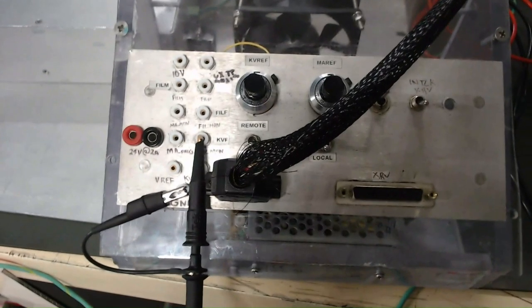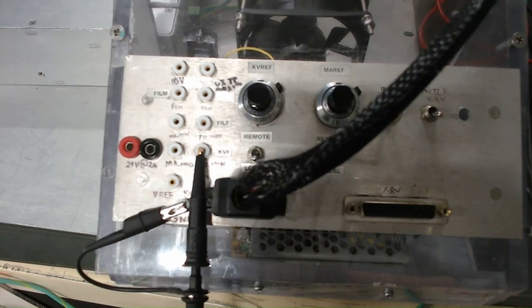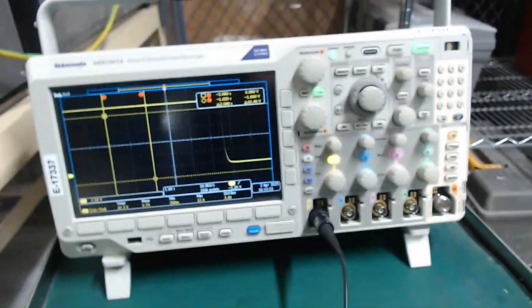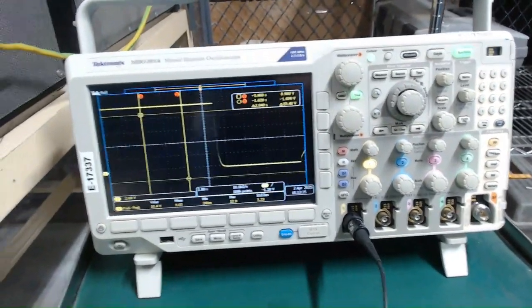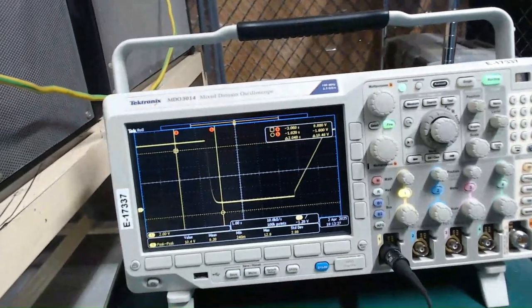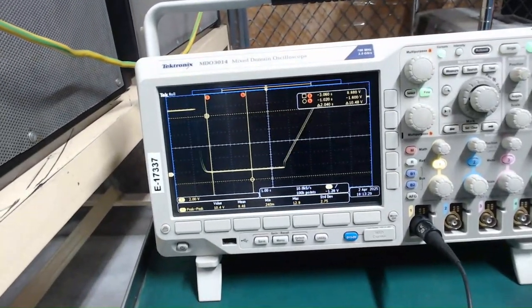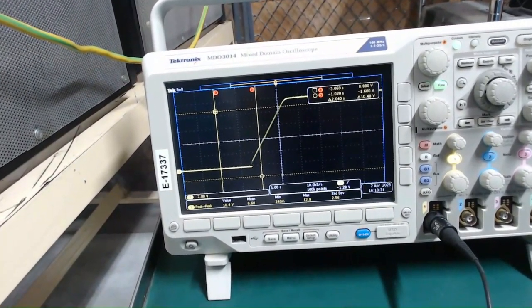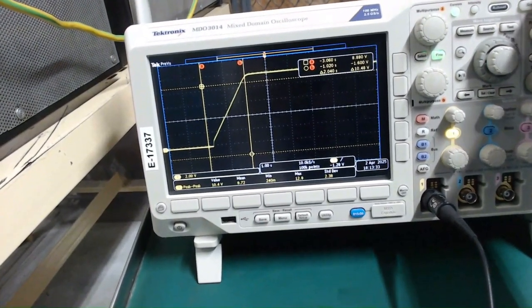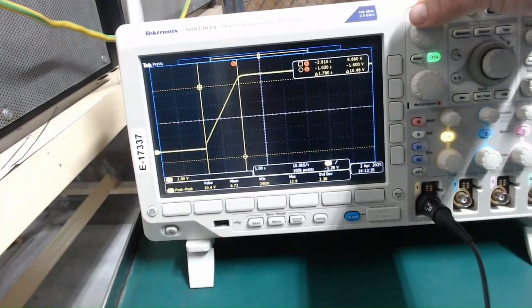After completing various cycles, the KV monitor signal is monitored using a calibrated oscilloscope and a calibrated passive probe to measure the slow start of the generator. Rise time of the output voltage monitor signal after closing the interlock should be approximately 2 seconds. As seen in the video, this is approximately 2 seconds. Value is recorded in the datasheet.